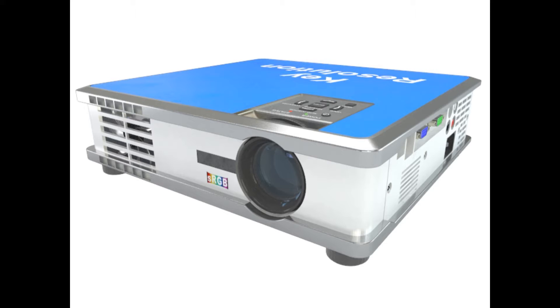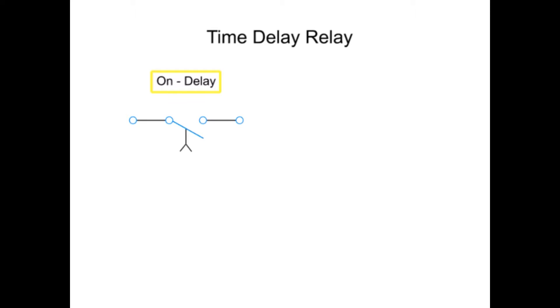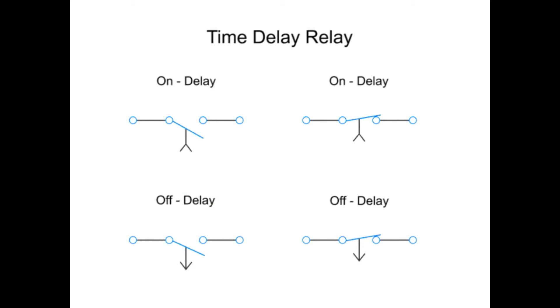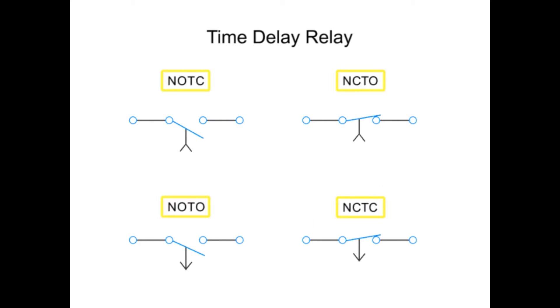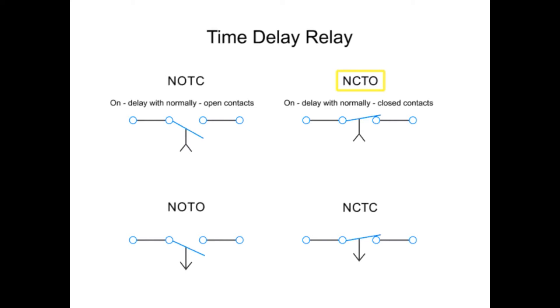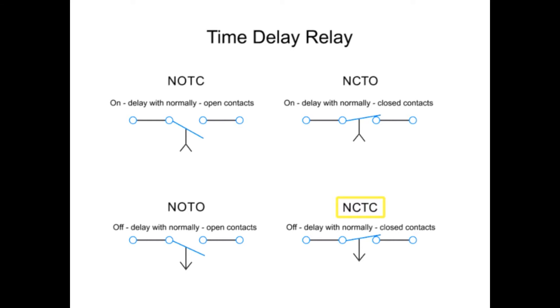Let's look at four basic types of relays. There are two types of relay functions — on-delay and off-delay — each with two types of contacts: normally open and normally closed, represented here by four symbols. NOTC functions as an on-delay with normally open contacts. NCTO operates as an on-delay with normally closed contacts. NOTO functions as an off-delay with normally open contacts. And NCTC operates as an off-delay with normally closed contacts.